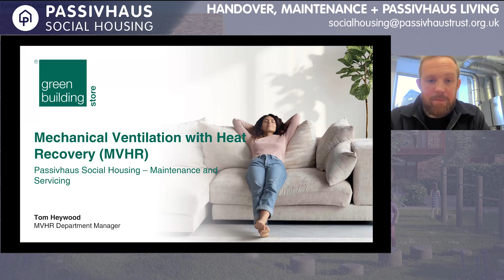So firstly, with regard to maintenance and servicing on MVHR systems, why is it needed? Well, your MVHR system is providing fresh air to your building, and it's extracting stale air and humid air. So it is essentially acting as the lungs of your building. Therefore, it does need regular maintenance. We've got airborne particulates, dirt and debris, which a lot of people think are small dust particles and things like that. They can actually be bigger, as you'll see in some of my pictures. So you can get insects that can get inside the unit and can cause damage to components.